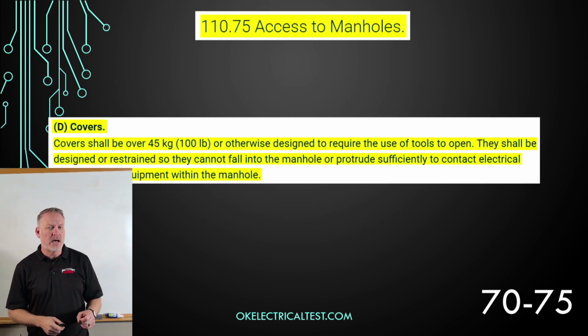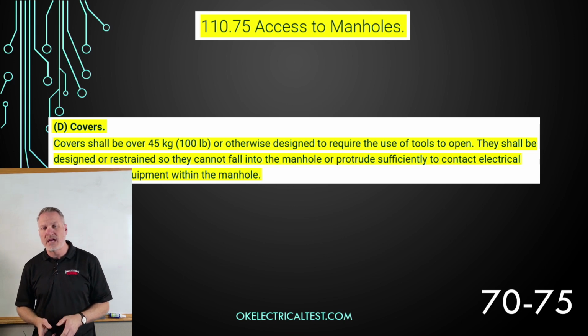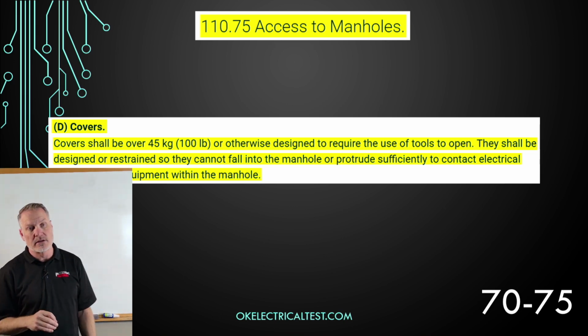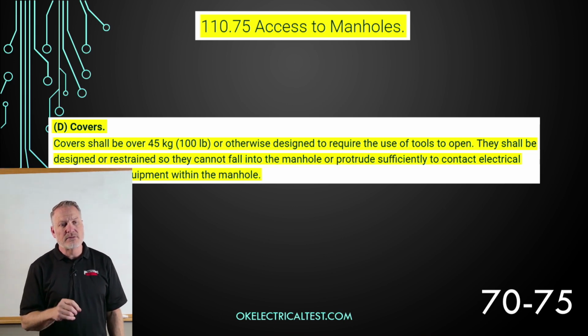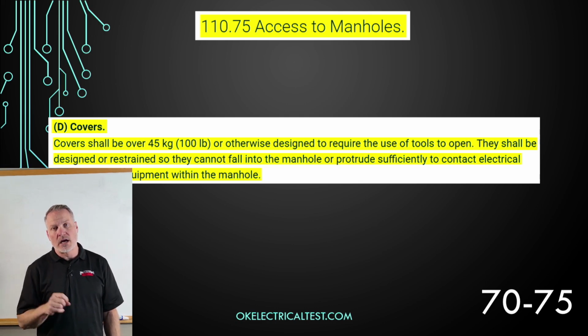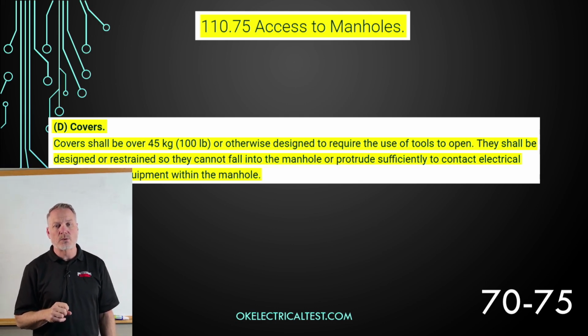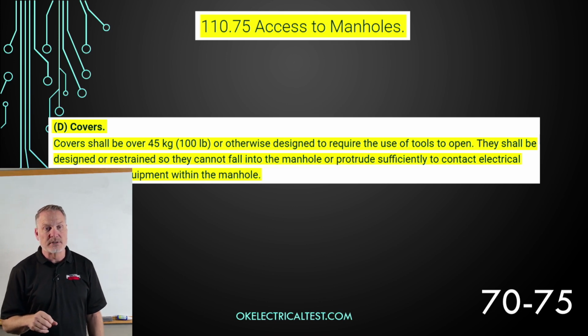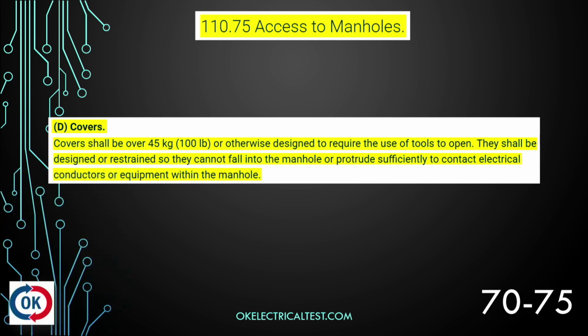Let's move on, still under 110.75, access to manholes. We're going to talk about the covers on the manholes. Letter D, covers. The covers shall be over 100 pounds or otherwise designed to require the use of tools to open. They shall be designed or restrained so that they cannot fall into the manhole or protrude sufficiently to contact electrical conductors or equipment within the manhole. And that's typically why we see that manhole cover being round, because a rectangular manhole cover can fall into the opening, but a round one will never fall into the opening.